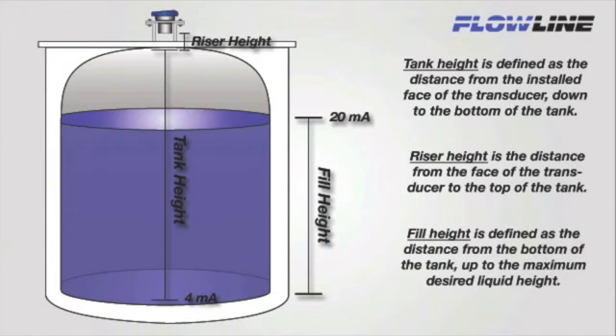If a riser is being used, then you will need to add the riser height to your tank height measurement. Riser height is defined as the distance from the face of the transducer to the top of the tank.